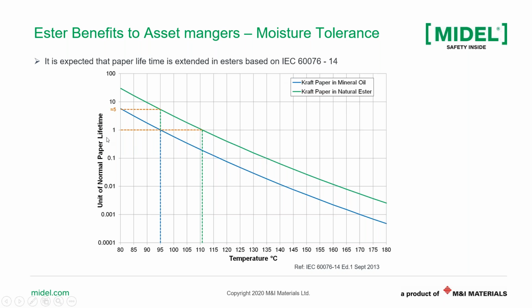For a nominal lifetime for mineral oil and kraft paper, the hotspot temperature, the high temperature in the winding, should not exceed 95 degrees based on this curve. But if you are filling with a natural ester, you can reach up to 110 degrees and get the same lifetime of the transformer. Equivalently, you can keep running at a lower temperature, 95 degrees, and then go vertical on the curve to extend the life of the transformer further. Now the curve here shows 5 times more. At MIDEL, we are conservative and only indicate 20% or 30% more lifetime out of the transformer, not 5 times.